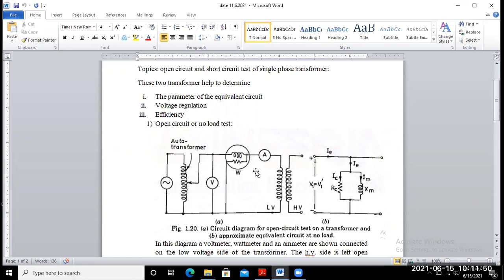I have already mentioned here the parameters we can find for the transformer: the parameters of the equivalent circuit, voltage regulation, and efficiency. When you note down all the instrument readings, you will get the no load voltage, the no load current with the help of the ammeter, and the no load power loss consumed, indicated by this wattmeter.